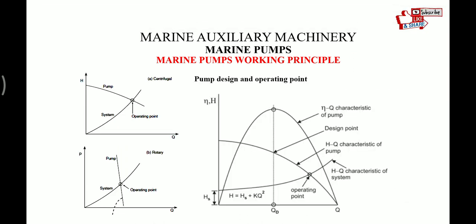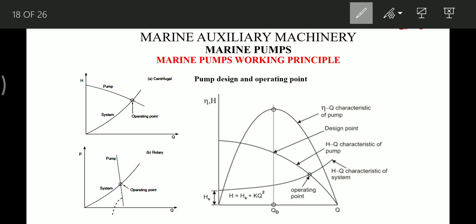Now I will explain the design point and the operating point. The efficiency curve has a point of maximum efficiency, and the corresponding point on the pump characteristic curve is the design point. The system operation curve intersects the pump characteristic curve at the operating point.